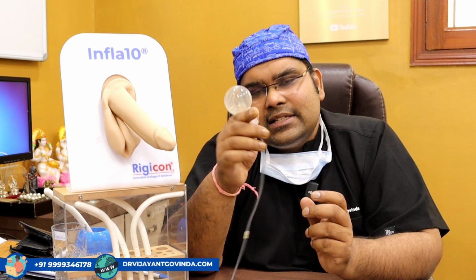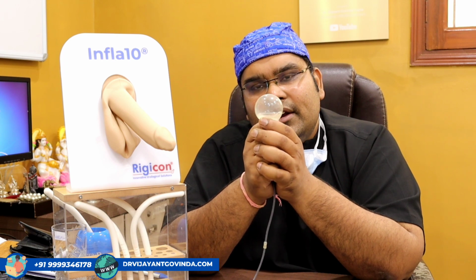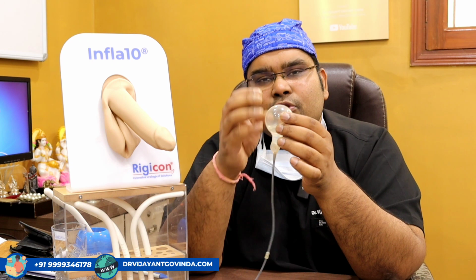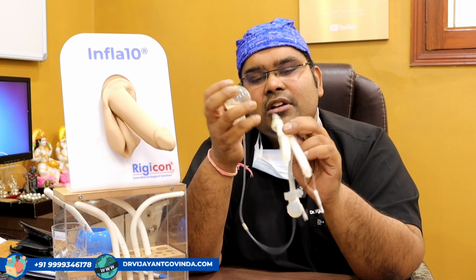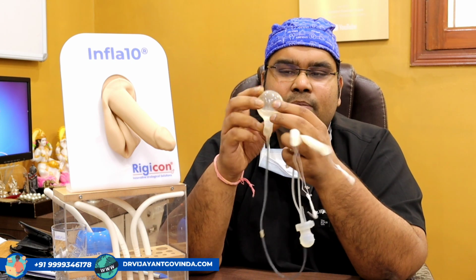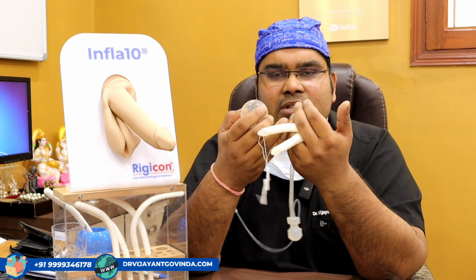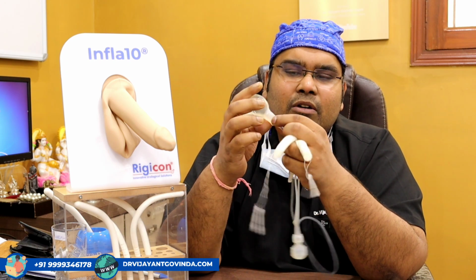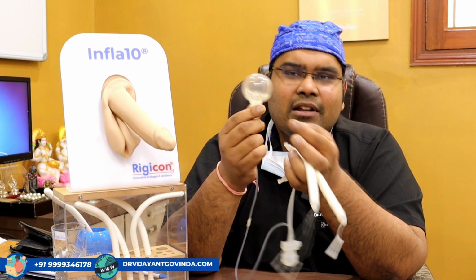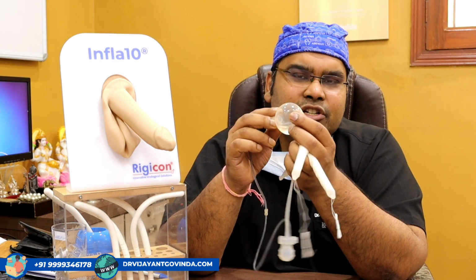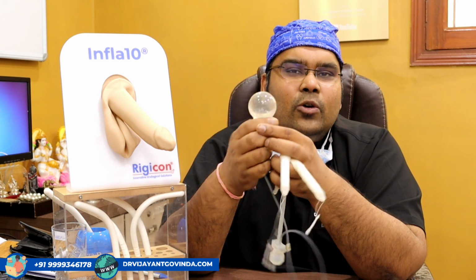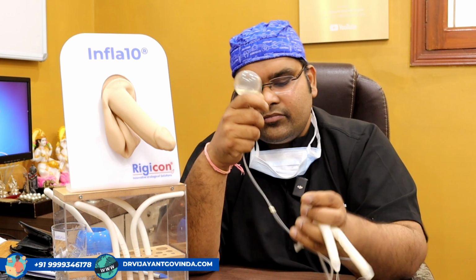What that does is that if, for example, you are a weightlifter, or in situations where your abdominal pressure increases, you won't end up with auto erections. Sometimes in the AMS, you would lift a weight, and because of pressure, water enters the cylinders and you get an erection, which can be embarrassing. To prevent that, the auto-inflation lockout valve has been given in the reservoir, which is a good addition, especially for younger men who are into active sports.